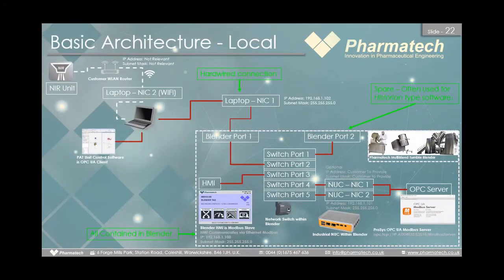This is a very busy slide, but it effectively shows that you've got your NIR unit up in the top left, connected via Wi-Fi to its control PC, with the control PC plugged directly into the Blender. The Blender runs a Modbus and OPC server, and the NIR unit uses OPC UA client software to access that server, allowing communication between the two. That's the most basic level of integration.